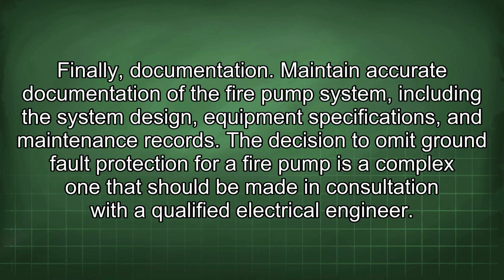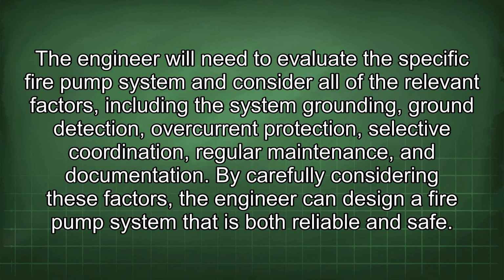The decision to omit ground fault protection for a fire pump is a complex one that should be made in consultation with a qualified electrical engineer. The engineer will need to evaluate the specific fire pump system and consider all of the relevant factors, including the system grounding, ground detection, overcurrent protection, selective coordination, regular maintenance, and documentation. By carefully considering these factors, the engineer can design a fire pump system that is both reliable and safe.